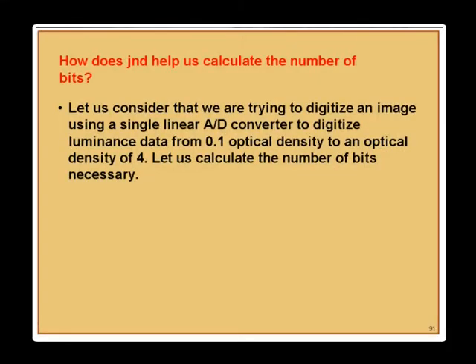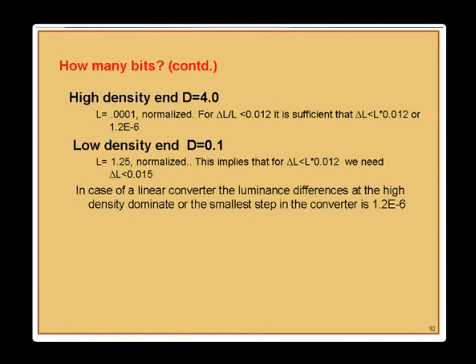Consider digitizing luminance data from 0.1 to 4.0 optical density using a linear A-to-D converter — as seen in mammography, which has a very high dynamic range. The calculations show the smallest required step is about 1 in a million, meaning a 20-bit converter would be needed, which is impractical at the required speeds. A log amplifier before the converter could reduce this to a 10-bit converter, or overlapping converters with curve fitting could be used.